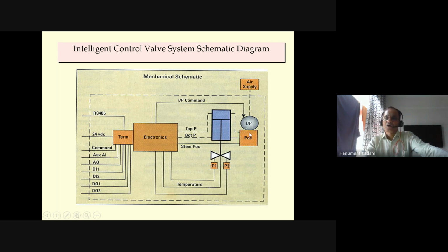Then you can see this is the positioner part where the position link is there, so a position sensor is there. So you see the stem position here. Stem position, one of the inputs that goes to the controller, which is normally the basic function. This is one input. Then top pressure and bottom pressure here, that is on a valve above the diaphragm and below the diaphragm. Those signals are also there. Pressure sensors are there. And you can see here, air supply is external and goes to the I2P.